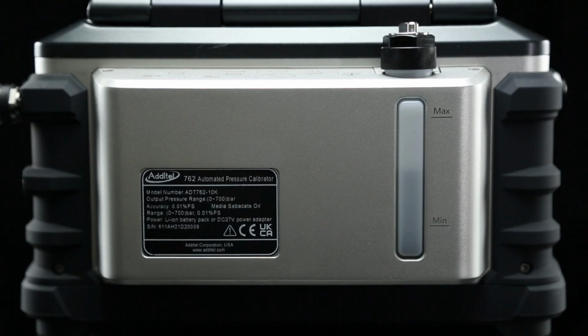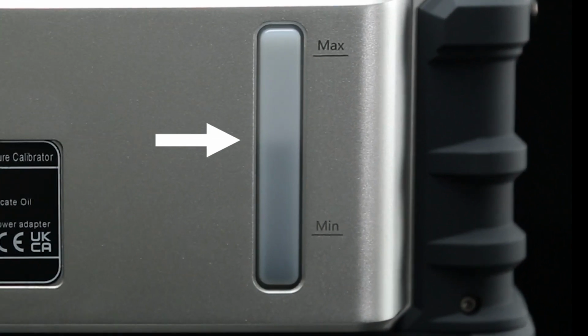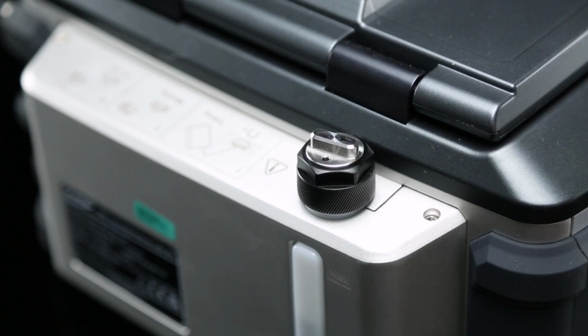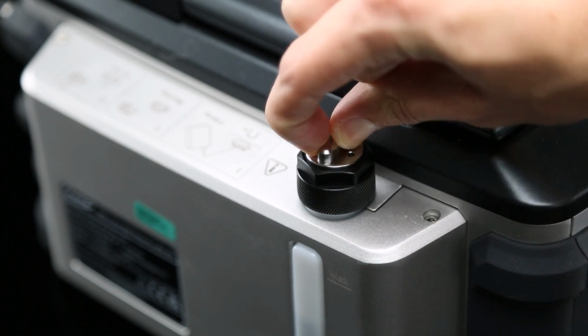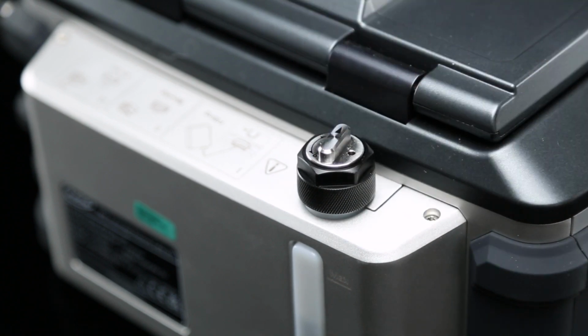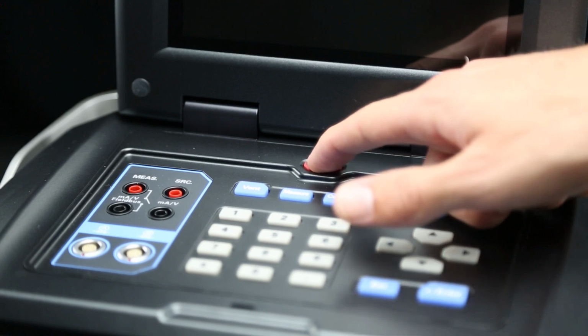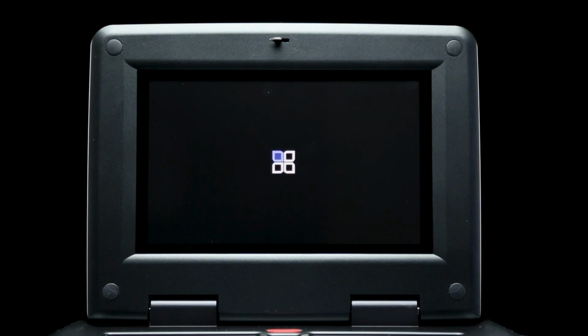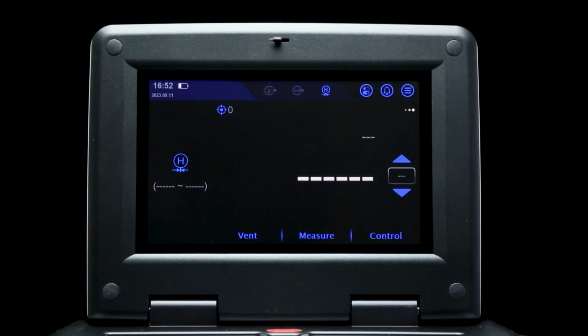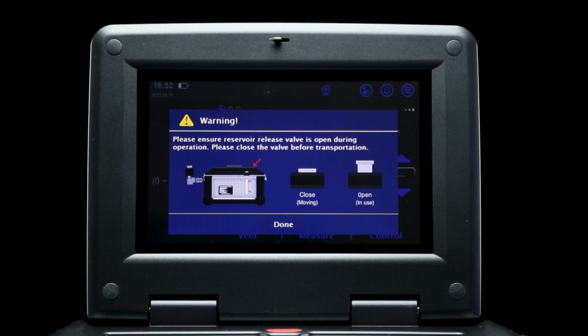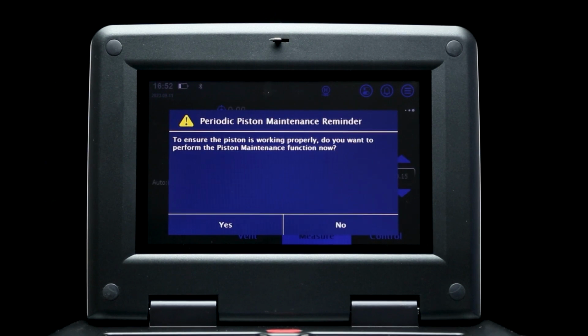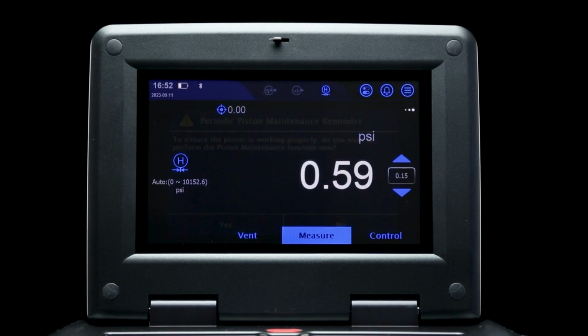To begin, check the reservoir on the back of your 762 to make sure the device has more than the minimum amount of oil. Next, open the reservoir valve by turning it counterclockwise from the close setting to the in-use setting, and then turn on the 762 using the power button. As the calibrator boots up, a pop-up window will again remind you to open the reservoir valve, as well as provide any other warnings that could affect device operation. Once the main display screen is showing, you're ready for calibration.